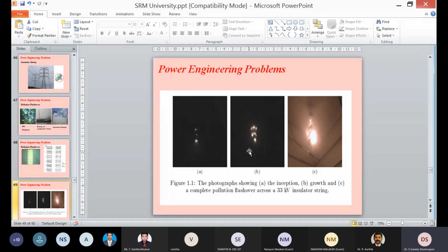Wherever tripping happened, we have to first know what is the level of pollution severity there, followed by what is the level of insulation available. If the insulation is not optimal, then we have to select a higher level of insulation. This exercise started in 2012-13. By 2015, for the entire North India, for around 12 states, a pollution map is available. By 2018, for the entire southern India, which includes Andhra Pradesh, Telangana, Karnataka, Kerala, and Tamil Nadu, pollution maps are available for the 400 kV line and 220 kV line. Research teams went and studied those lines for 2 years.